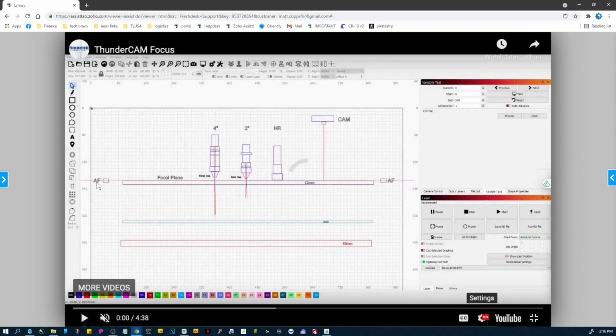There we go. So your autofocus sensor array goes across the bed from one side to the other, and it always detects the surface of the material. The reason is the head is normally stationary, because you only autofocus with the 2-inch head when it's in its uppermost position. That's always going to give you the same distance, because you have that constant there. The same way with the camera: as long as the camera doesn't move, if you use autofocus with the camera both when you align it and do the alignment procedure and when you're using the camera, then you're going to maintain your accuracy. Because if you start moving away from or closer to the lens and don't have that under control, that's where your alignment gets out of whack.